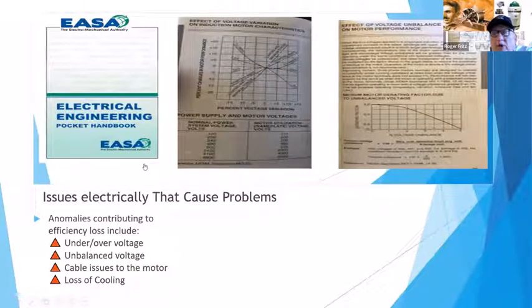And what happens too often is we want to design something for cost effectiveness, but we forget to take into effect. So like the fellow at Fluke was talking about, there's a chart in here that talks about, when compared to the nameplate, where you are on balance of those three-phase input powers, and where you have to derate the motor. Even if you're off 5% in voltage imbalance, you're supposed to be derating that motor to 75%. And most applications don't do that. And so I see a lot of motors running at bad points of their power input, causing premature failure. So it's important to do that.